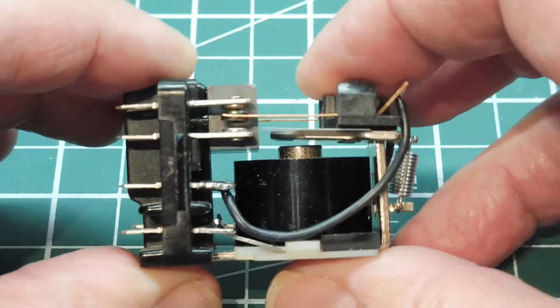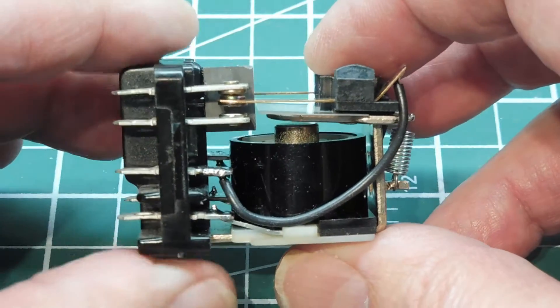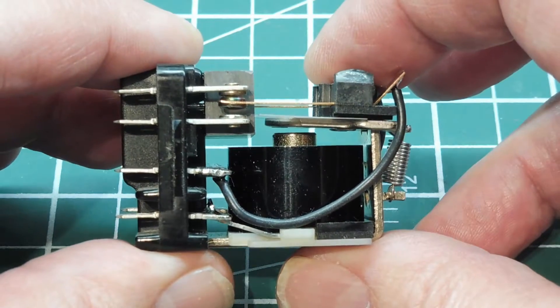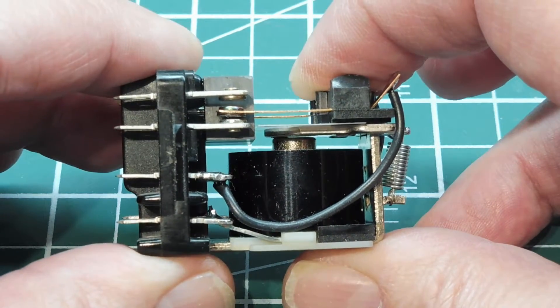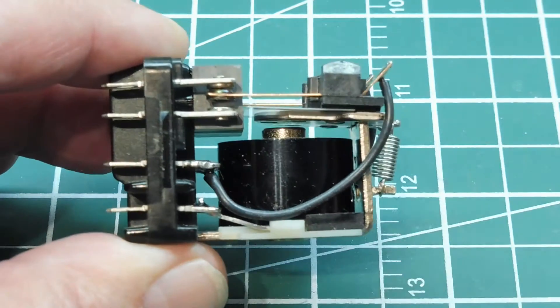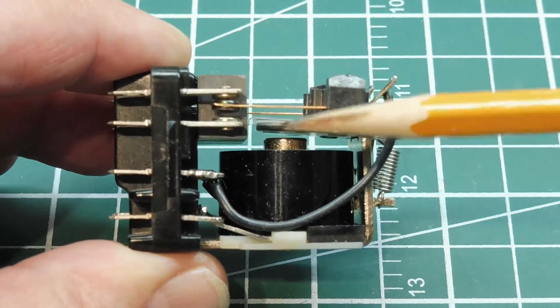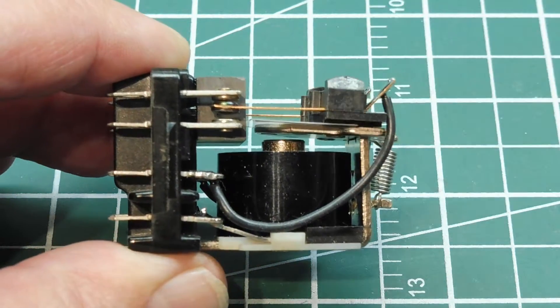Now when a relay switches an inductive load, like an induction motor, when armature pulls in, turns on the motor, and then when it shuts it off, there'll be a spark across the contacts because you're shutting off an inductive load.